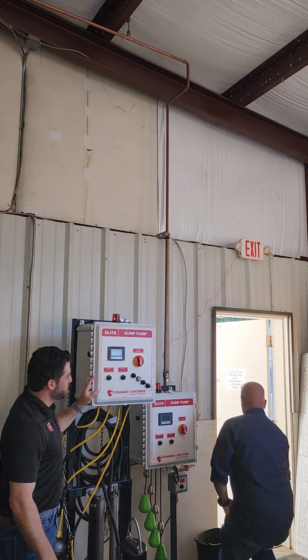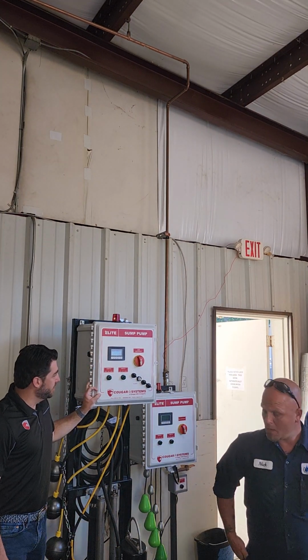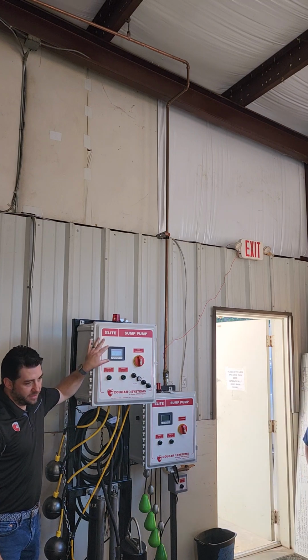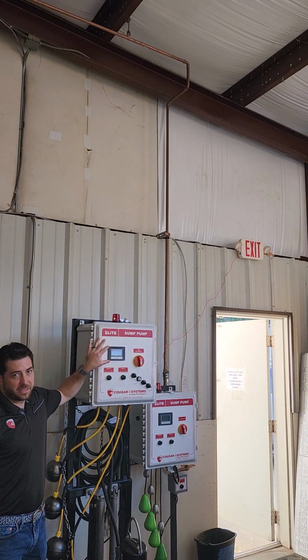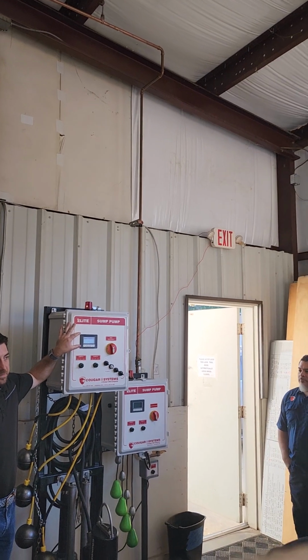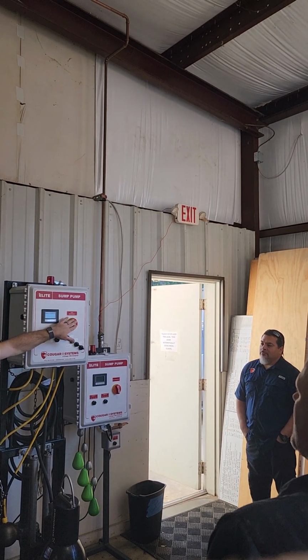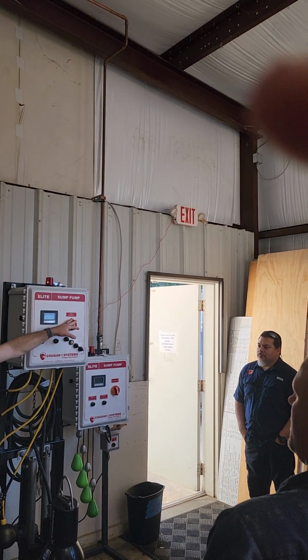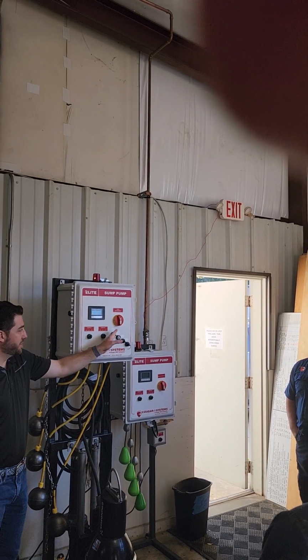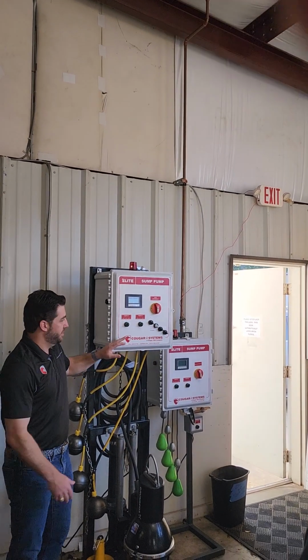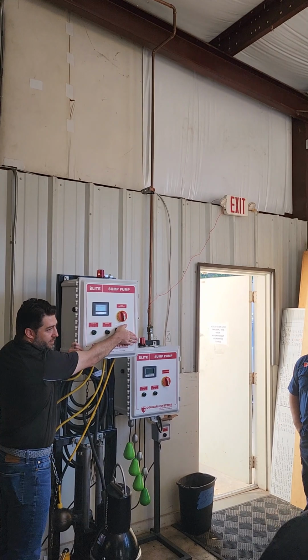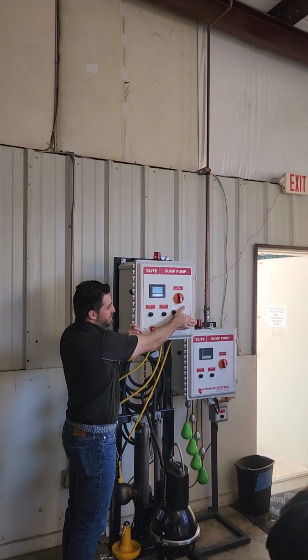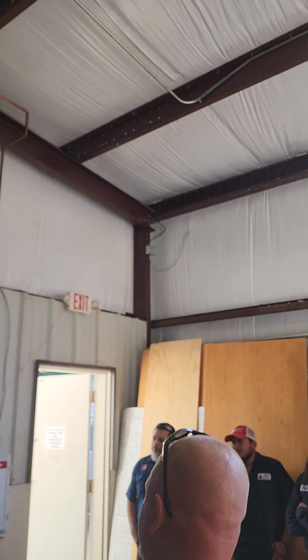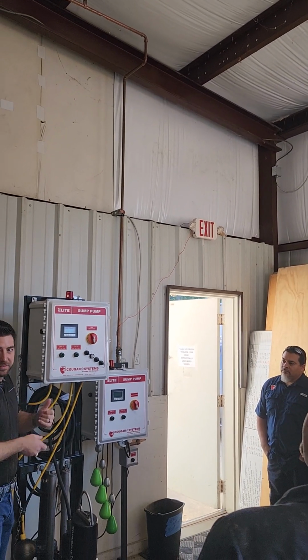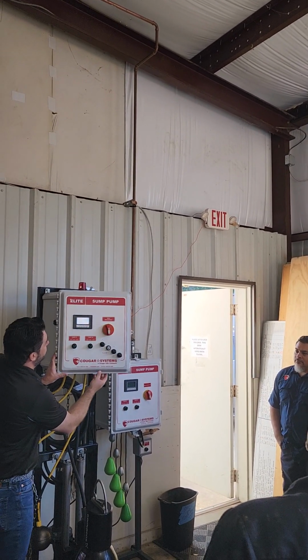So when we jump up to this panel, this is our Elite Series. So you notice right off the bat, you get the touchscreen on the front. This is going to give you the feedback of everything that's going on in the system, and you also get a through the door disconnect. Okay, so this allows you to turn off power before you open the door. Remember, you still have that hot power coming in underneath. These switches right here don't exist on the real panel. They're just here so that we can act like we're flipping float switches without having to flip float switches. Okay. That's what's up.